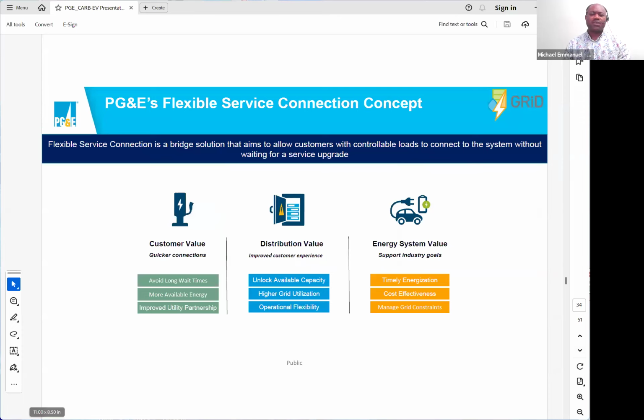One of the things to note about flexible service connection is that this is a bridging solution that will allow customers with flexible load, that is load you can throttle up and down, to connect to the system without having to wait for a service upgrade. Previously, without this platform, customers with capacity constraints at their location would have to wait about 2 to 4 years until that capacity upgrade is completed before they could come online. But now with this type of program, we can bring those flexible loads to the system without having to wait for a system upgrade. Again, to emphasize, this is a bridging solution pending when the capacity upgrade will be completed.